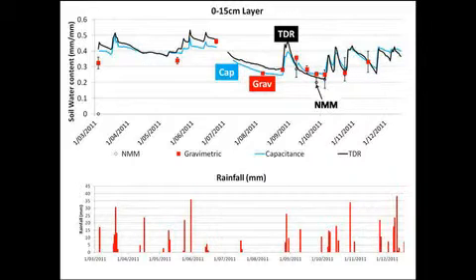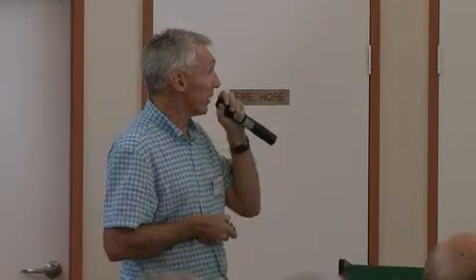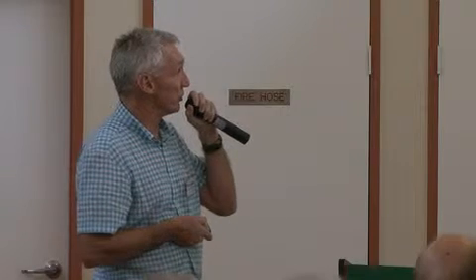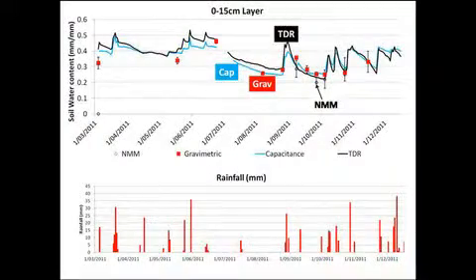So all of the technologies are doing a reasonable job, but you will see, particularly in this top layer, the 15 centimetre layer, where you've got a lot of evaporation going on, you've got a lot of cracking going on, etc., you do see variation between the technologies. One of the issues, particularly with, remember I said before, the installing devices from the surface as opposed to the side, one of the issues with the vertical or the surface push is that you tend to get cracks forming around these devices. They're basically created by the device themselves. As soon as you put something in the ground, you tend to start getting cracks around it, and you see this with NMM tubes as well. What's happening here is you're getting drying or bad or poor measurement, poor estimation of water by that device because of those cracks. But in general, not too bad.